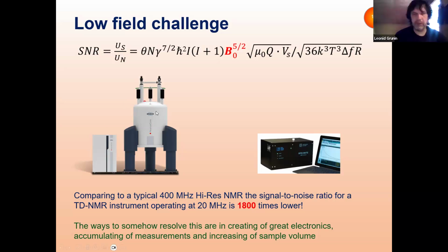The good and expensive high-resolution device has a much better signal-to-noise ratio because the magnetic field is higher, and this dependence is nearly, I don't know, with a very high power. The stronger the field you apply, the much stronger the signal you can get. If we compare two devices, one operating at 20 megahertz, a typical Spin Mate from Resonance Systems, and the one from our friends from Bruker, which operates at 400 megahertz, the difference in the signal-to-noise ratio will be about 2,000 times. So we really get a loss of signal.